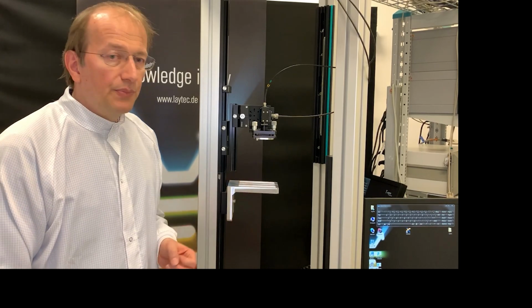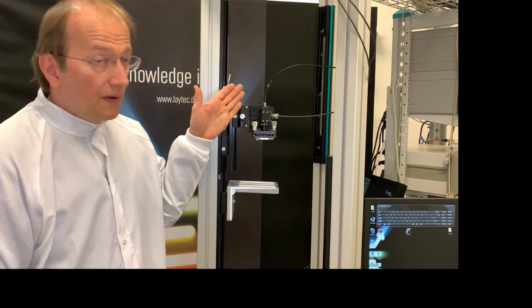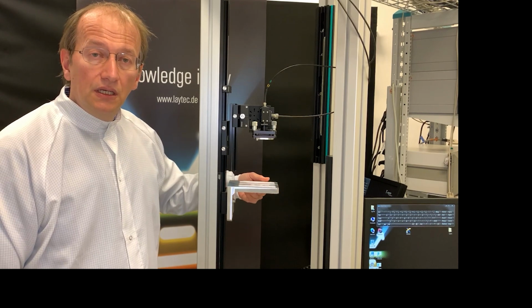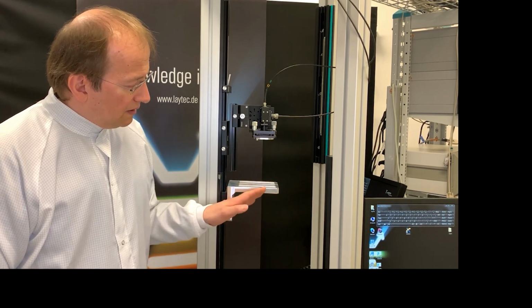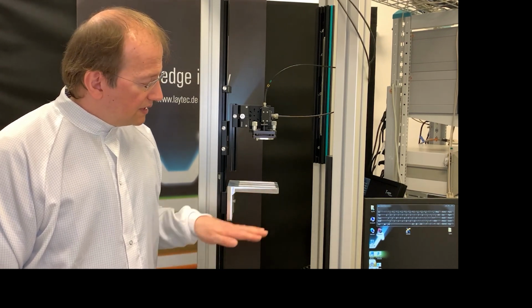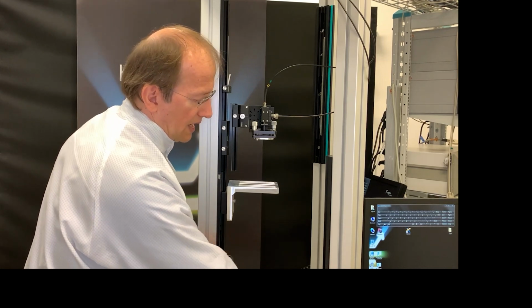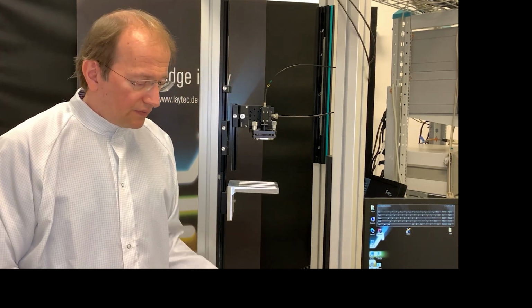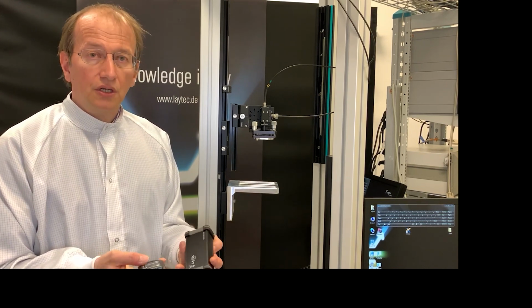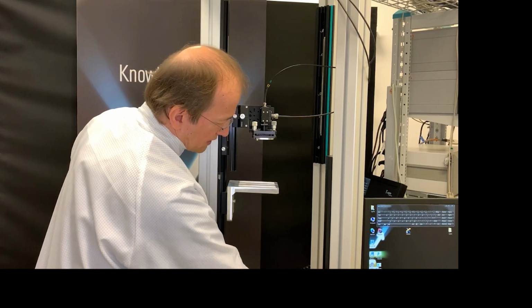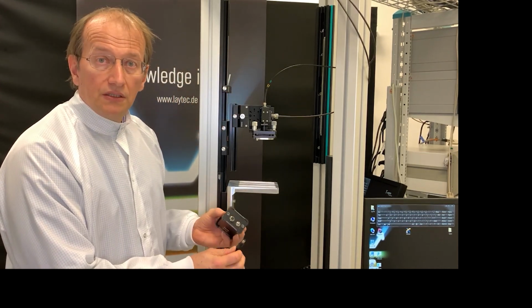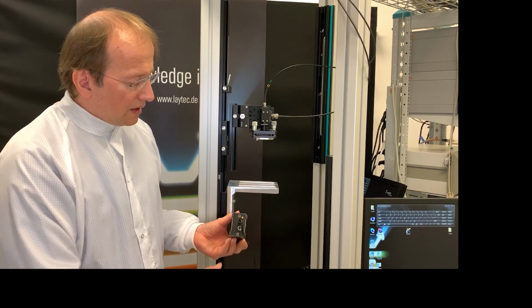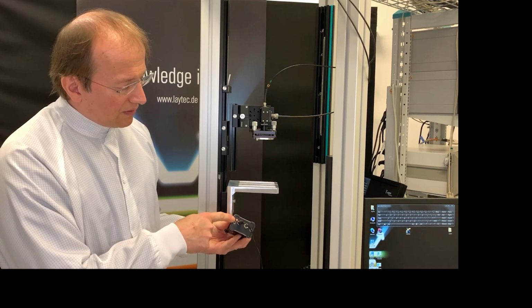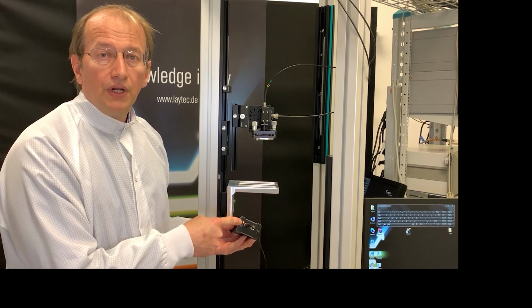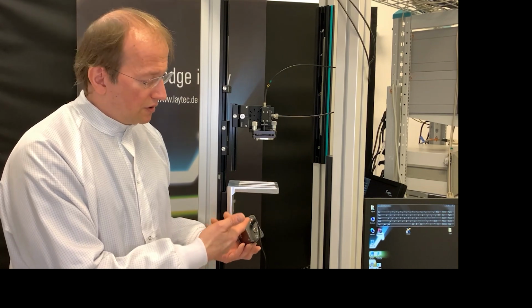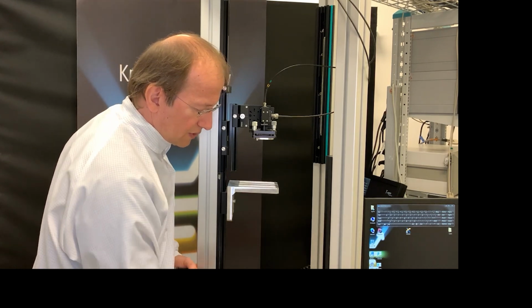So we are now in our lab and we have a test stand. So we have the EpiTT. This plate is simulating the upper reactor lid. This is the area where the reactor interior is. The wafers will be somewhere here. And so we have to prepare our hardware. First we verify that the battery is charged. The charger, you just simply connect into a wall socket and plug the round connector into the connecting terminal. You see when it's charging, it is an orange LED, which will then turn green when it's fully charged. This one is almost fully charged, so it is good for us.